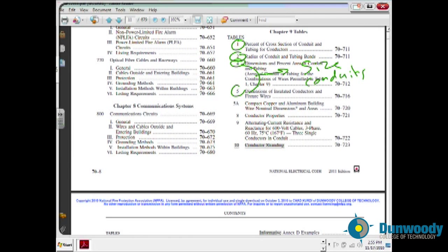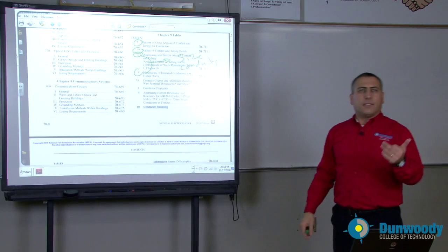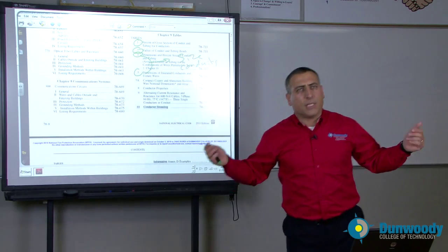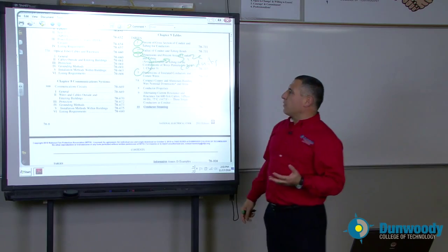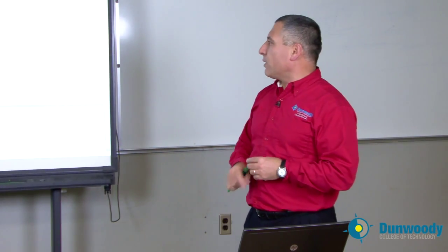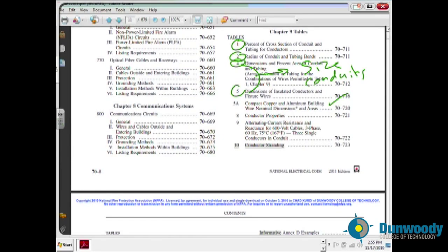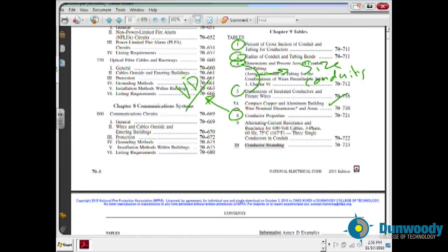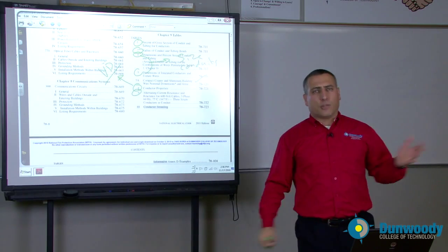Table 4 and Table 5 are very important — they help us size conduits based on branch circuits, feeders, and service entrance conductors, with different insulation and different sizes. For example, you can put 16 number 12 THHN conductors in a three-quarter inch EMT conduit. How do you know that? You do the calculation from Table 4 and Table 5. Table 8 is very important when it comes to voltage drop. We use Table 8 and Table 9 for AC and DC voltage drop calculations to find the resistance and impedance of the circuit, to size the conductor based on length — how far can you push a 100-amp panel from the source while still meeting the code recommendation of 3% voltage drop.